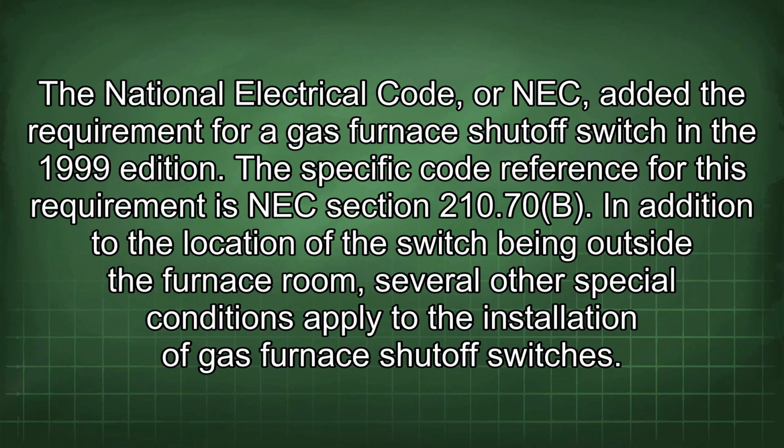The National Electrical Code, or NEC, added the requirement for a gas furnace shutoff switch in the 1999 edition. The specific code reference for this requirement is NEC section 210.70(B). In addition to the location of the switch being outside the furnace room, several other special conditions apply to the installation of gas furnace shutoff switches.